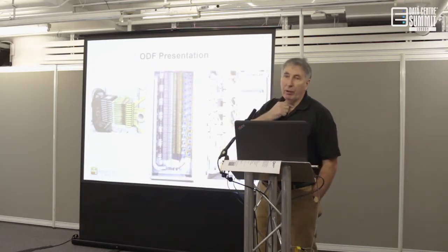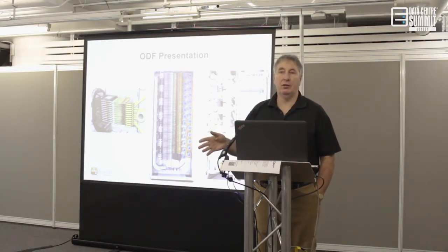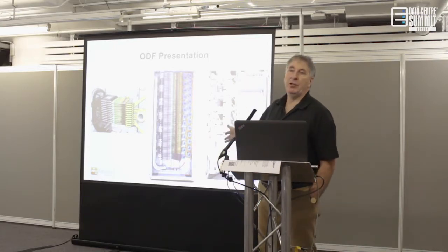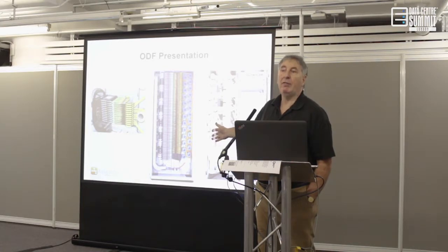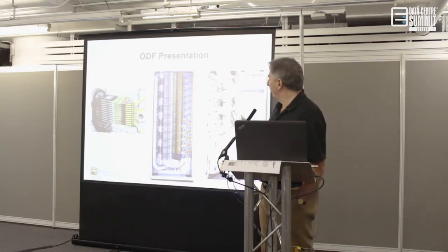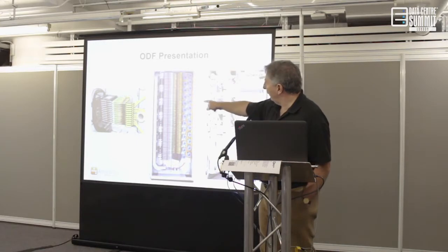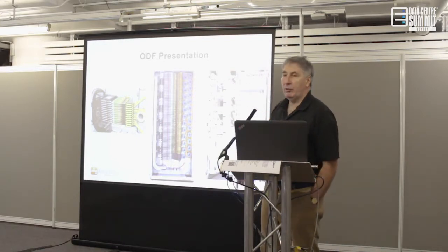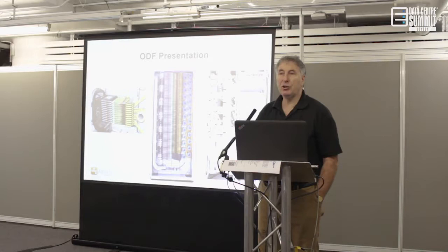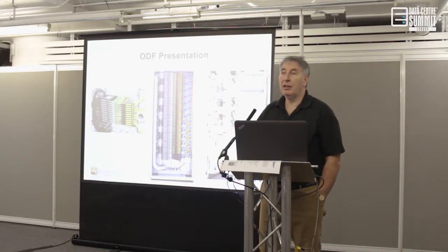A lot of the work we're doing with mobile phone providers is they can't get enough density in a normal rack, so they have a rack dedicated just to optical fibre distribution. And so we might have 80 odd cassettes in one of these. Each has maybe got 12 to 18 ports. Every single one of them goes somewhere. But of course, there's a lot of density, and you can see there's various things to help with the cable management as part of that. These are just examples. Unfortunately, I don't think there's many of them out there at the moment. But to give you an idea, that's still not dense enough for some people. They still want more, because that's what the equipment needs.